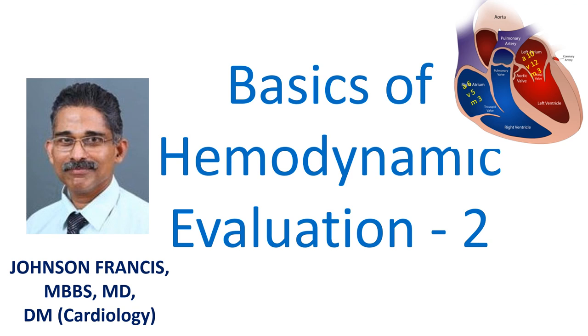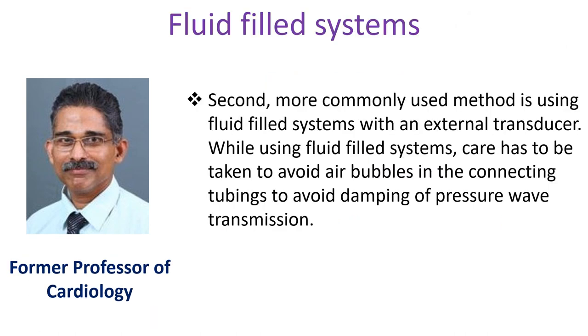This video is the second in the series on basics of hemodynamic evaluation. Pressure measurement in each chamber is an important aspect of hemodynamic evaluation. Two types of catheter-based pressure measurements are possible: one is a catheter-tipped manometer, which is more ideal but expensive. The second, more commonly used method, is using fluid-filled systems with an external transducer. Care has to be taken to avoid air bubbles in the connecting tubings to avoid damping of pressure wave transmission.